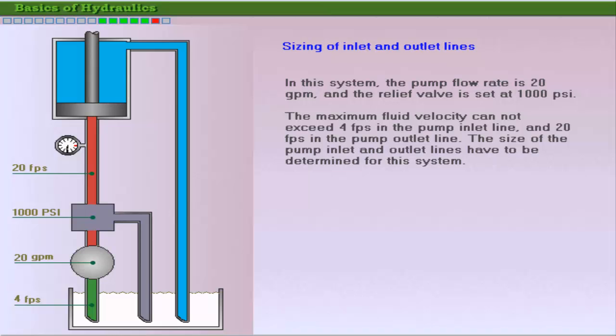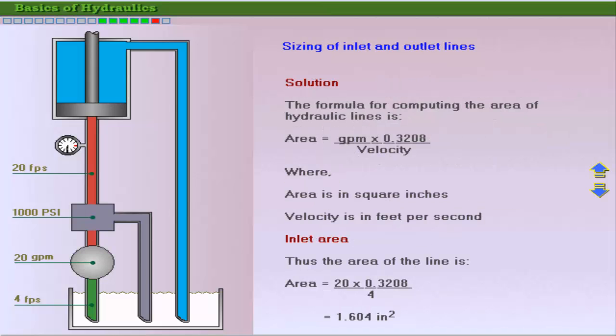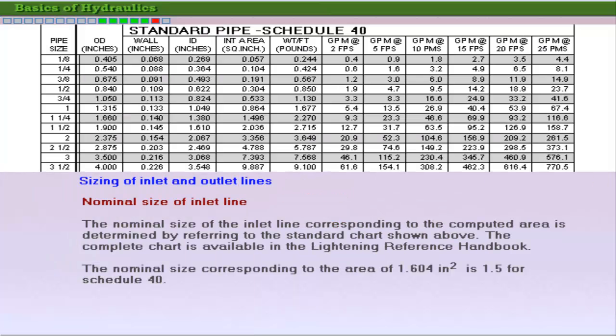The area of the pump inlet and outlet lines can be calculated by using the following formula. In order to find the nominal size and the schedule number of the pipe corresponding to the calculated area, refer to the steel pipe characteristics chart in the Lightning Reference Handbook. The minimum nominal size for the inlet line corresponding to the computed area of 1.604 square inches is 1.5 inch for Schedule 40. As the pressure at the pump inlet is very low, the pressure rating of the inlet line is not checked.